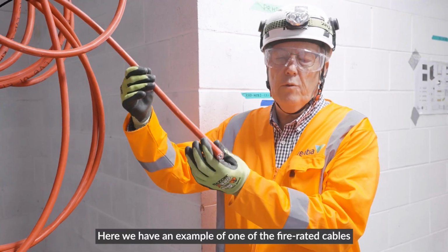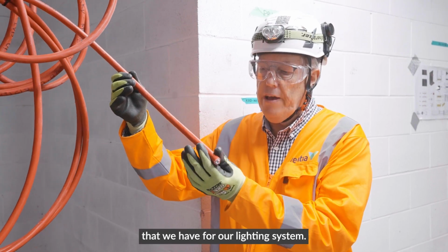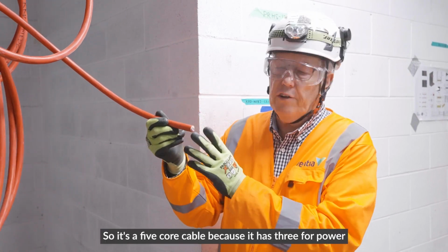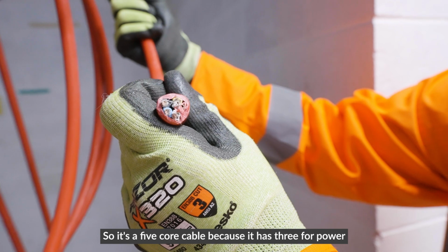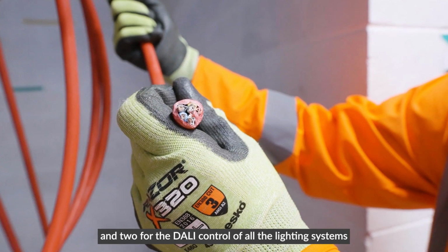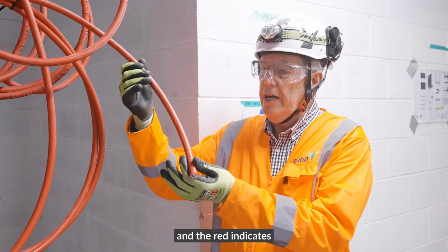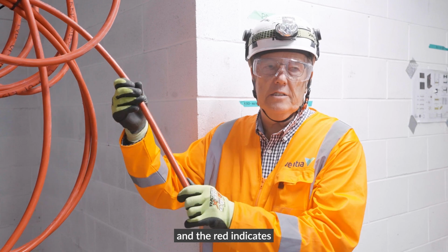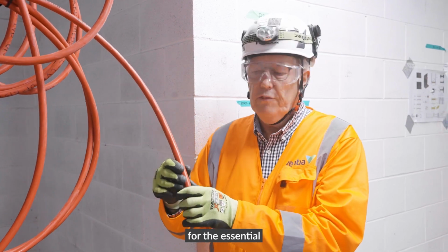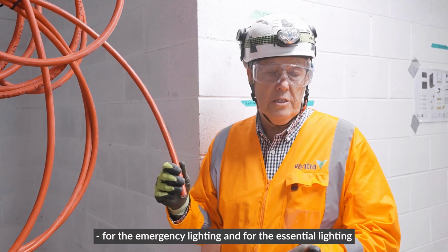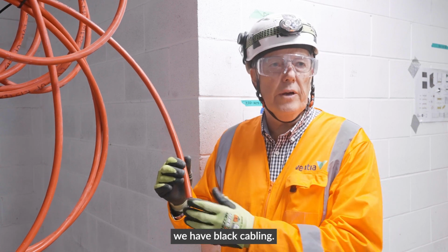Here we have an example of one of the fire-rated cables for our lighting systems. It's a 5-core cable because it has 3 for power and 2 for the DALI control of all the lighting systems. The red indicates it's a 2-hour fire-rated cable for the emergency lighting, and for the essential lighting we have black cabling.